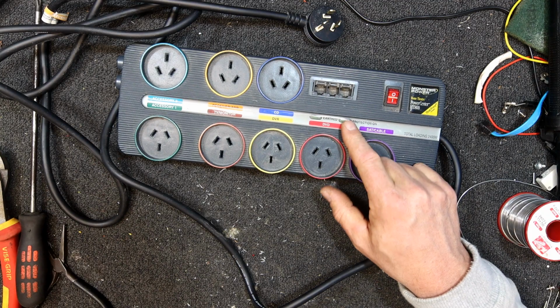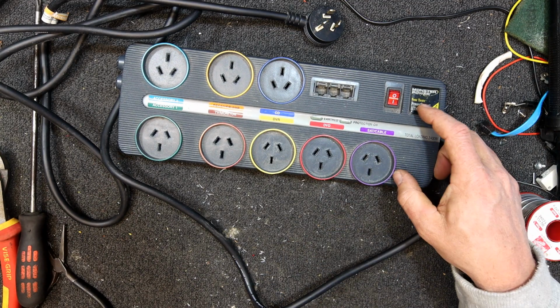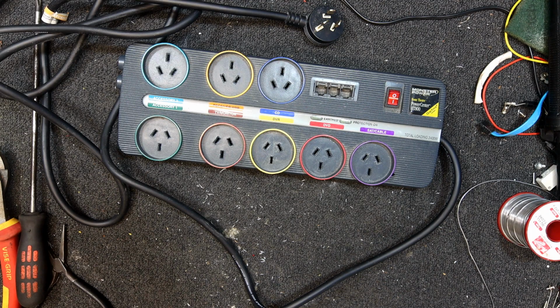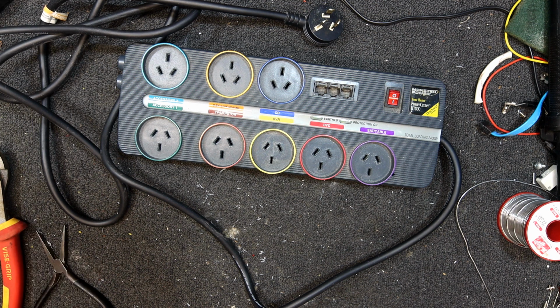You may not get the buzzer, but you'll likely get the power light out, because it'll go through the neutral if that side gets blown and not the other one. But in this case, we just had a fault indicator because it lost its voltage, since the resistor feeding it had gone open circuit after sitting across the mains for so long and dropping a lot of voltage.